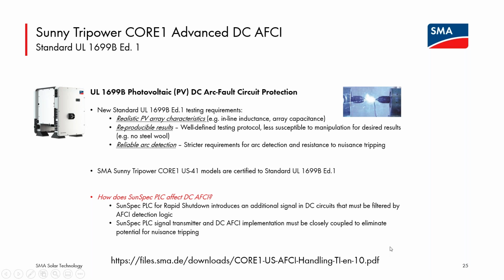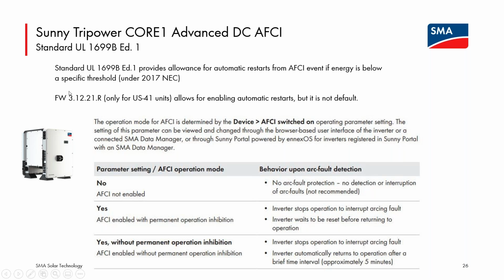And with the new UL 1699B Edition 1 full standard, there was testing methodology to test that, to verify the limits and allow for that automatic restart. So the 3.12.21 firmware allows that. So there's an additional setting for parameters in the inverter related to AFCI, more than just off or on. And yes, on is the default from the factory, even with units with this firmware. So units from the factory with higher firmware, and those in the field that have received automatic firmware updates, will still have yes chosen for the AFCI behavior, which requires a manual restart.